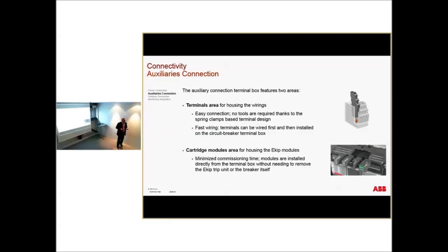A lot of improvement has been done in the wiring. Basically, there were two sorts of improvements. Improvements on the contacts: now we have single fitted Phoenix contacts, which are changeover contacts. They can be plugged in without any tools, and plugged out with a screwdriver. So it's very fast wiring. Because they are screwless, you just put the cable inside, and there are no screws going around.